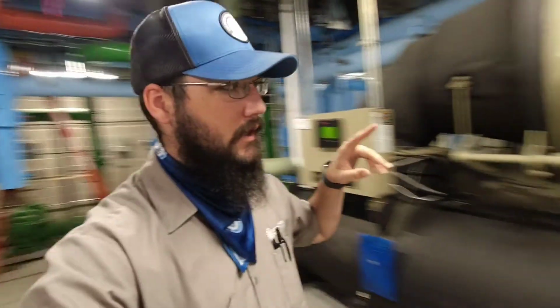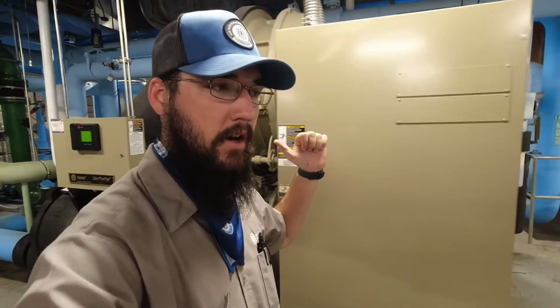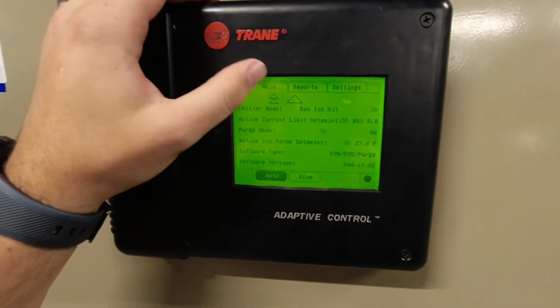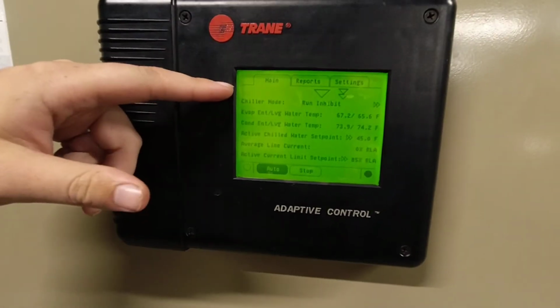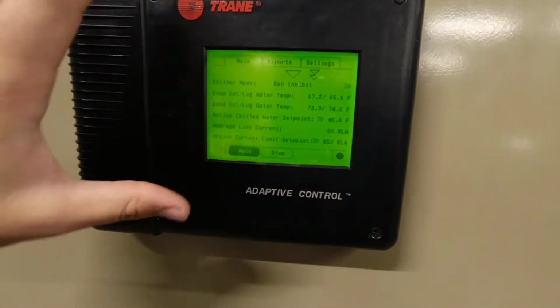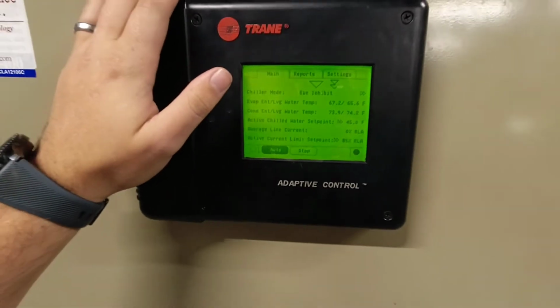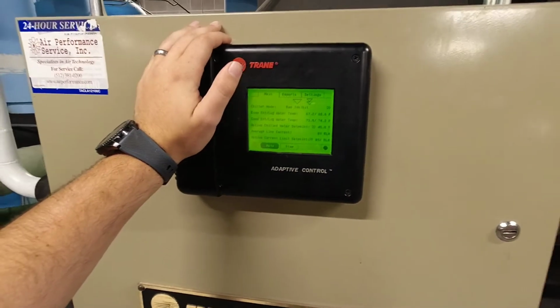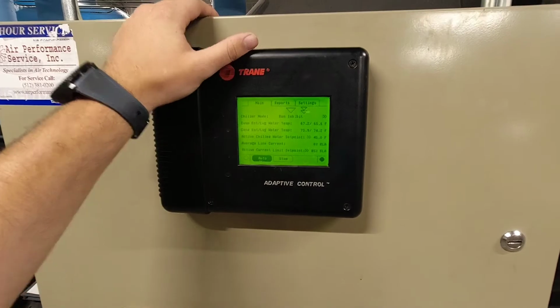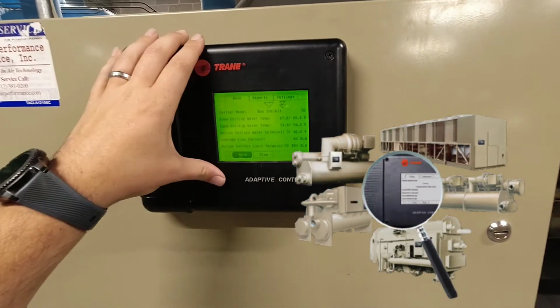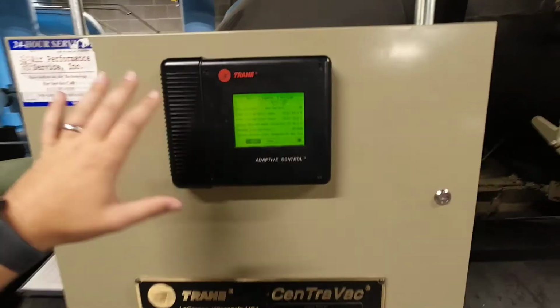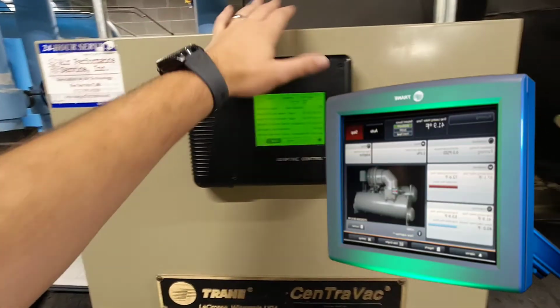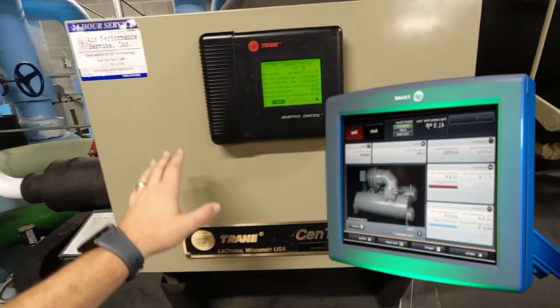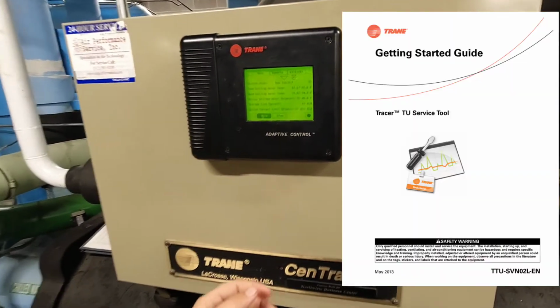Heavily requested item is a full rundown on Trane CVHF, CVHE series centrifugals. Starting here at the main controls. This is the adaptive control. This is the older series. They do have a newer one. This particular controller will still work with the TechView series service tool. The newer one that actually has a graphical display and color and the whole nine yards will not. It requires the Tracer TU software.